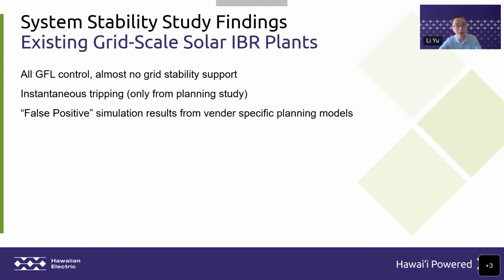Two years ago, we had a system event: a fault happened on the transmission level. From that event investigation, we see that almost none of the existing grid-scale IBR plants can provide grid stability support. So I will show some DFR traces in the next slides.